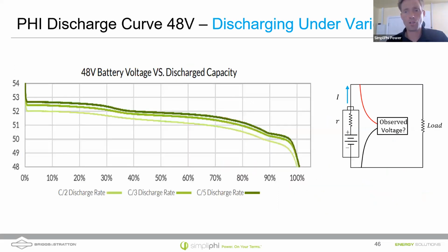So if you're in a discharge cycle and we hit down here, let's suppose you set it at the recommended value of 50.1 that we give you, you'll hit that 50.1 somewhere around here, right? And after the discharge stops, the voltage will bounce up probably to about 51, 51 and a half, something like that. When you hit 48, because you're on the knee, it'll bounce up much more. So yes, there is a rebound below 10% remaining charge life. Hopefully I answer that, Drew.